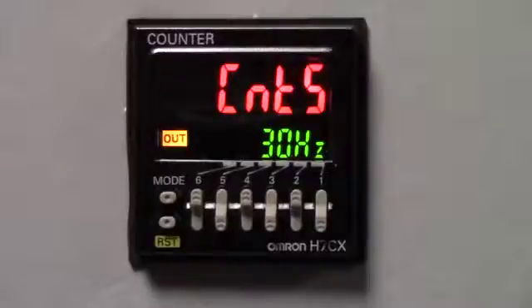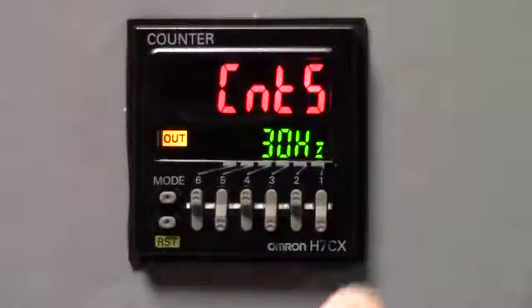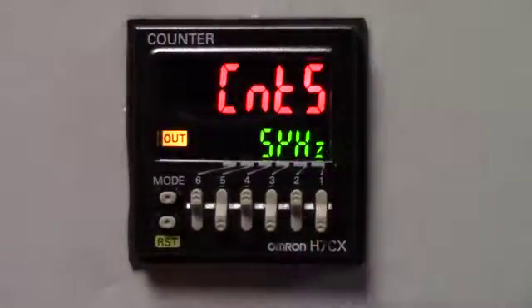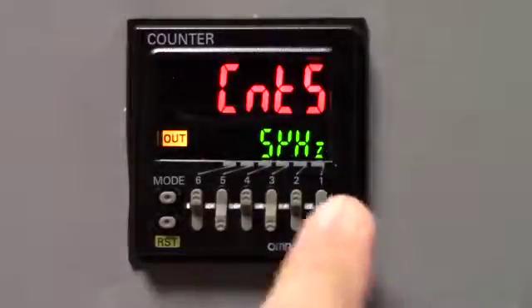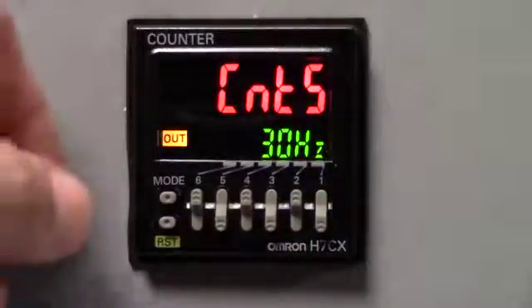You're going to see CNTS. This is the counting speed. There's two speeds to choose from. There's 30 hertz. By pressing the number one key, that will change us over to the 5 kilohertz. Seeing how we're going to be using a push button for our input, we can use the 30 hertz. So, we're going to press the mode key.